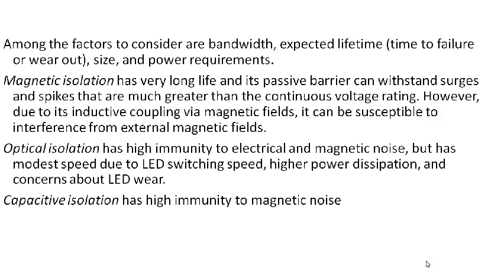Factors to consider when selecting isolation type include bandwidth, expected lifetime (time to failure or wear out), and size and power requirements. Magnetic isolation has a very long lifetime and high withstanding capacity to surges and spikes beyond its continuous voltage rating, but it may be susceptible to interference from external magnetic fields. Optical isolation has high immunity to electrical and magnetic noise.